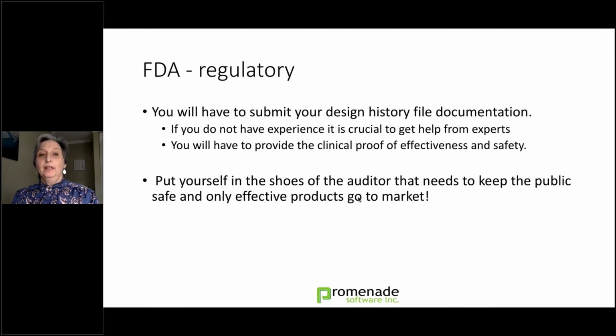When you go to the FDA, the regulatory, you will need to submit your entire design history file, documentation that's part of that. If you don't have experience with that, it is crucial you get help from the experts, because there's a lot that goes into it. A lot of pieces, a lot of small pieces that need to be covered.